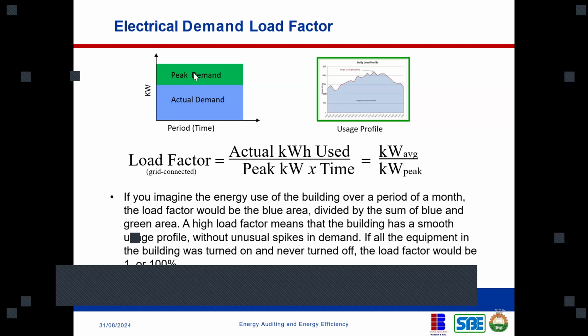The green area represents your peak demand, which is what you have here. But your actual energy consumption is your blue area, which is your numerator. Then your denominator is your peak demand times the time that you use this power. That's what I'm trying to explain here. So once you do this, you'll be able to clearly establish what your load factor is.